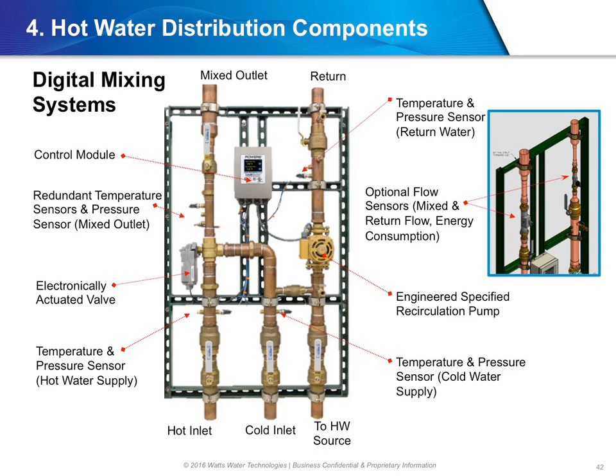Beyond purely thermostatic mixing valves, computerized digital mixing systems are also available that are considered a smarter and safer way to deliver mixed water throughout a healthcare facility. In this type of system, intelligent control modules and electronically actuated valves are used to allow faster and more accurate response to constant changes in the mixed water delivery demands. Further, digital water mixing and recirculation solutions can be integrated into a building automation system to allow facility managers complete control of and visibility into their domestic hot water delivery.